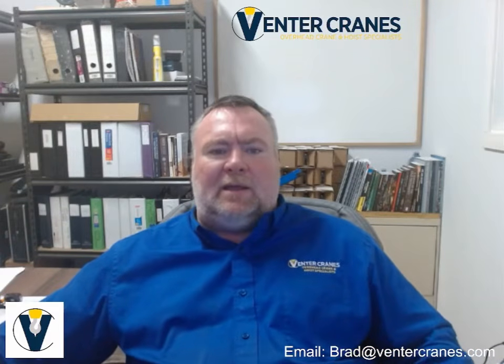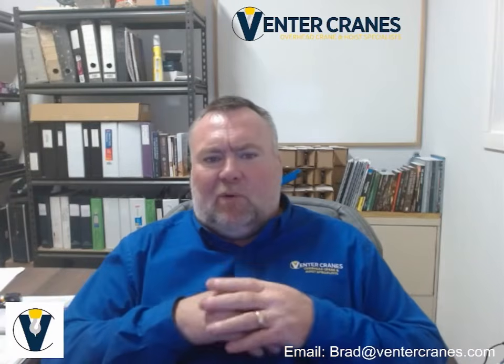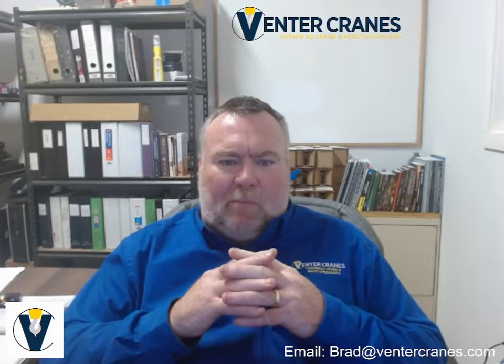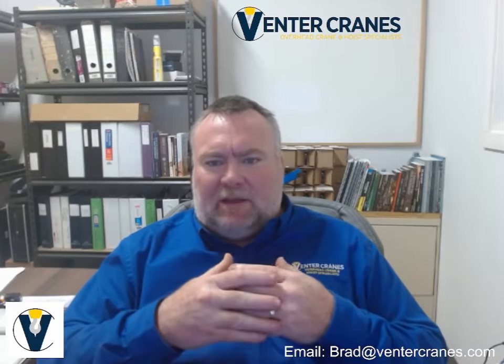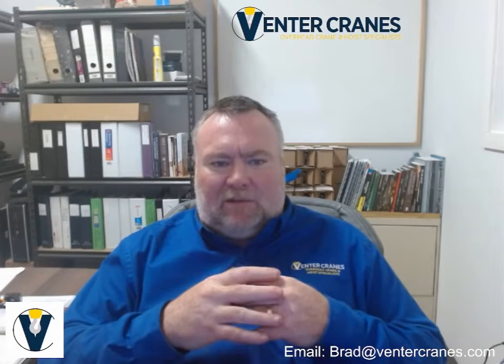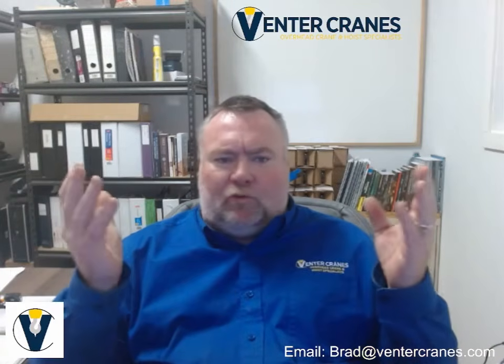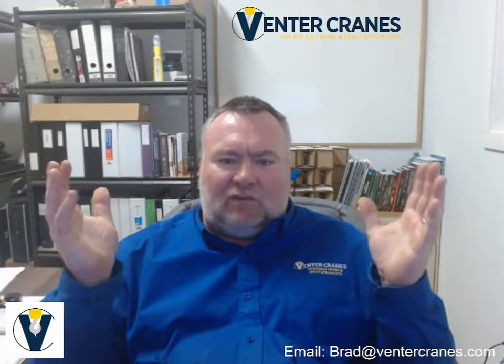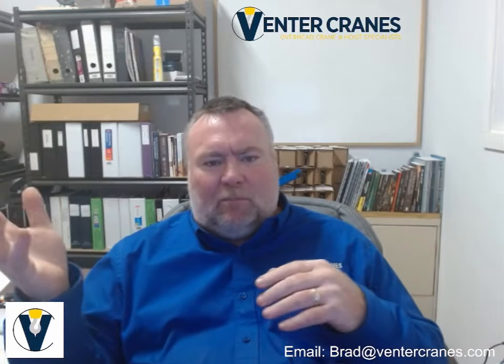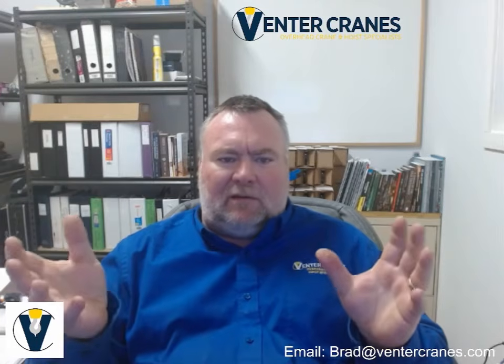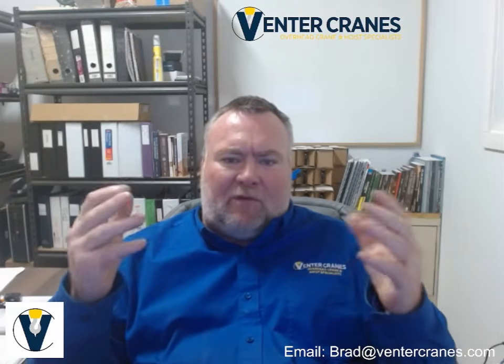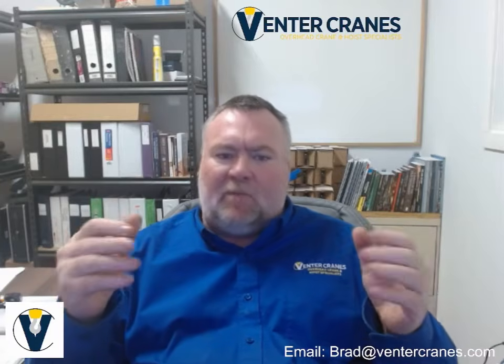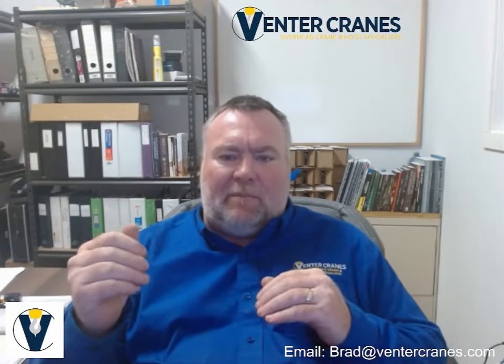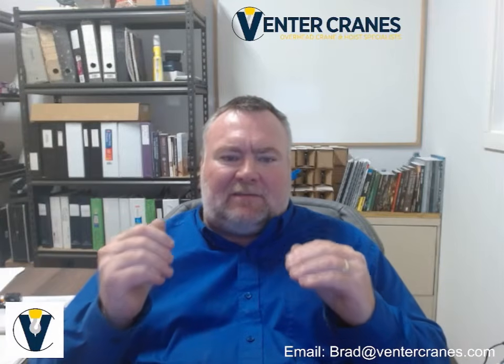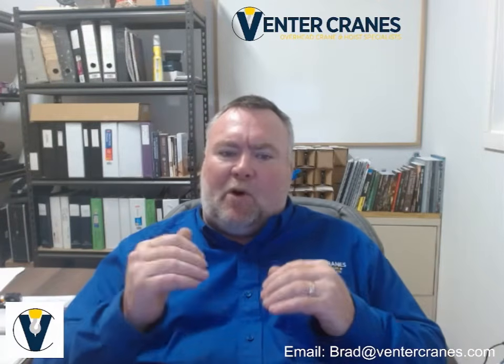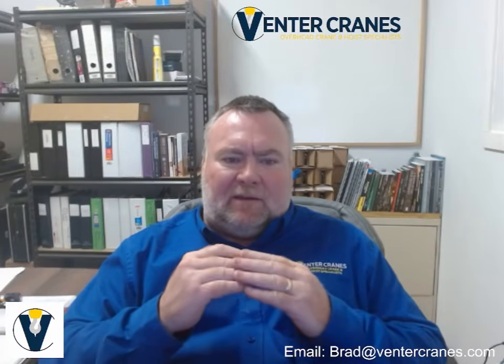So operator training, the goals under section 9.3.1.1, we need to ensure operators have the knowledge and experience to operate safely, follow manufacturer's instructions, and comply with the standards. So who's qualified to provide the training? Section 9.3.1.2 to 1.4 covers this for us, right? The training may be provided by a qualified third party or an in-house trainer. Trainers must complete a valid Train the Trainer program, keep certification current, and take refresher training themselves, right? Programs must match the specific equipment and site conditions.